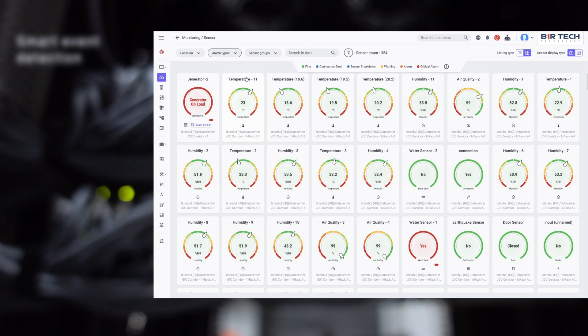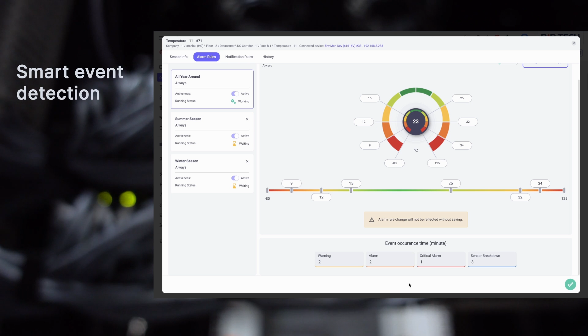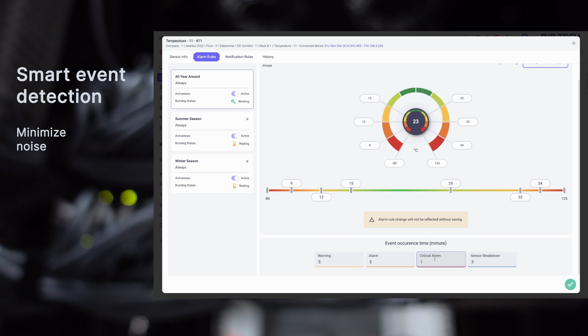And a big part of that noise reduction seems to be avoiding what they call alarm pollution. Right, using smart event detection. An alarm doesn't fire the instant a threshold is crossed. There's delay management. An event might only be generated if a condition, say high temperature, persists for a defined period, maybe 5 or 10 minutes, filtering out those brief spikes or momentary fluctuations that don't actually represent a real problem. Exactly, which really cleans up the operator's view, letting them focus on sustained, meaningful events.